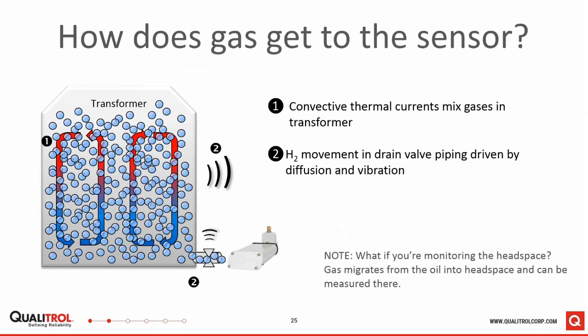How does the gas get to the sensor? So in common with most of the single gas applications out there, it's via convection. And that's the same way that the gas gets to the sampling point if you're taking a sample to send to the lab, thermal convection, right? So the oil in the transformer is in constant motion, assuming that the transformer is under load. There's usually no forced oil circulation in a bulk transformer, so it's convection that's driving this oil. The process of circulation may be slow. It may take hours for the gas produced to get to the sampling point.